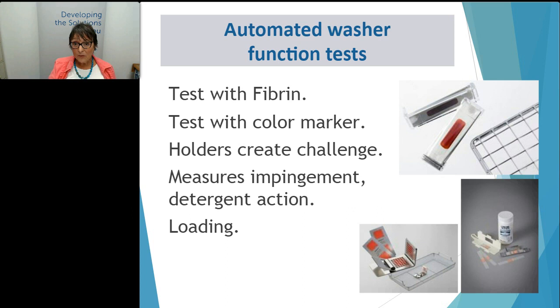But I want to tell you, you can have passing tests, fabulous passing coupon tests, and still have dirty instruments. How can that happen? Because of the human factor. Remember that slide we saw earlier that had human factors on it? If humans are not loading the washers correctly, overcrowding or putting things in such a way as that they do not get the full cleaning action, then I don't care how many little tests you pass, the instruments themselves may not be clean because we didn't load them correctly. So loading is a big issue.